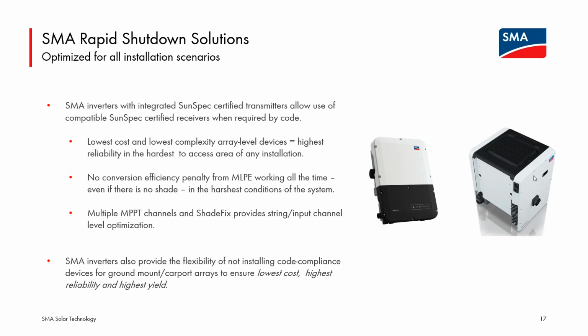ShadeFix is built into the inverter. You get all of that energy optimization, whether or not the rapid shutdown receivers are being used. So you can tailor each installation specifically to the code requirements. Those receivers are very easy to install. They are not providing module level data back to the inverter. So when you are commissioning the system, you don't have to wait for them all to report in. You don't have to scan the barcodes of all the devices and create that module layout map for monitoring. So it's a much simpler, faster install, far less complexity strewn throughout the array, which again, translates to higher reliability. And you have the ShadeFix optimization built into the inverter. So we're aiming for very, very fast, low cost, high reliability, easy to install, and high yield PV installations.